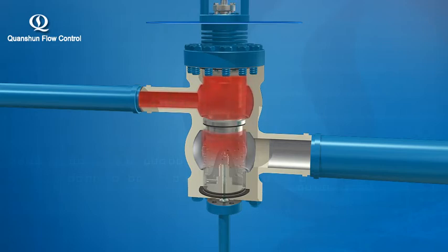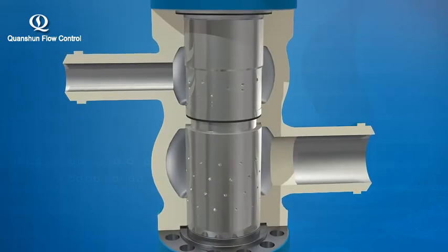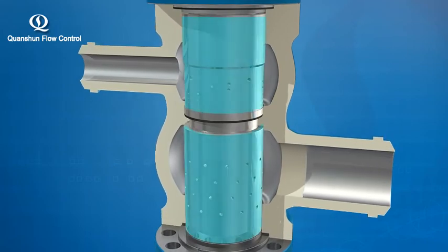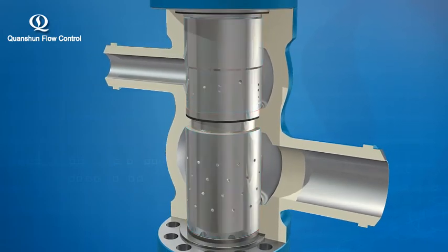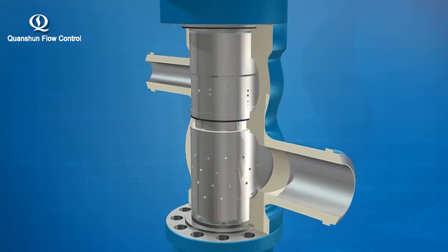In addition to the TMP relief valve, there are many small holes on the restriction orifice plates, and when steam flows through these holes, the pressure reduces accordingly in response to reduced cross-section areas of these passages. This design also reduces the noise. Internal components of the valve body are all removable from the upper and lower bonnets, which, without the assembly of the body, facilitate maintenance and replacement, and therefore save a great deal of repair cost.